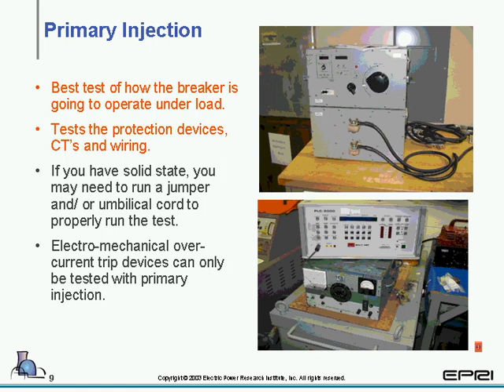Primary injection. Primary injection is the best test for checking the overloads on the breaker or the protection. You might want to remember that too if you're taking the test. That means the overcurrent trip device and the coils there. That is correct. Some newer designs, the digital type, have self-protection, and we'll take a look at that in section 3. For the older design, the electromechanical, this is the only way to truly test to see if they're within their band.